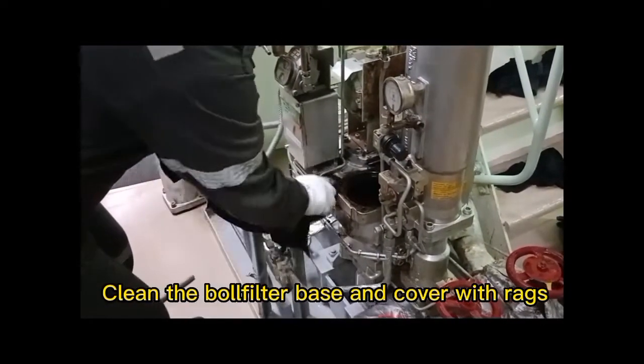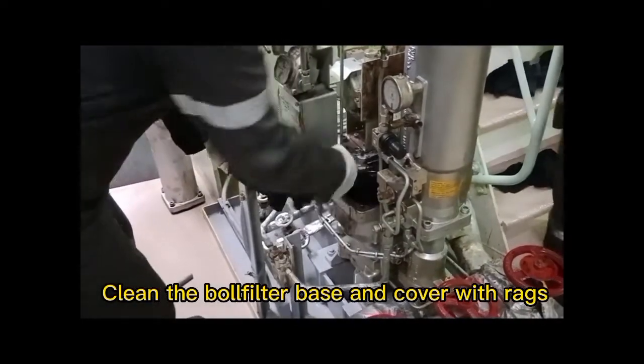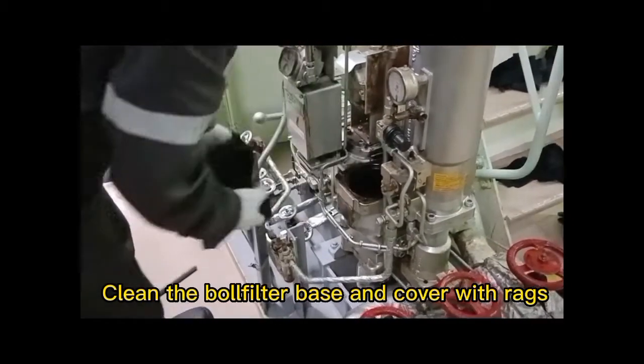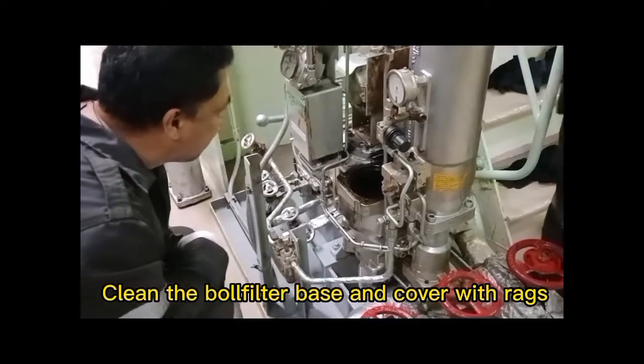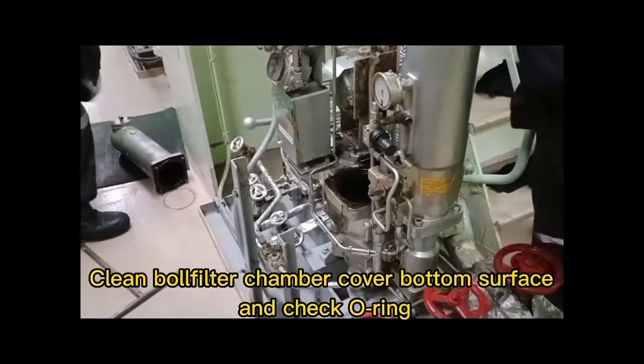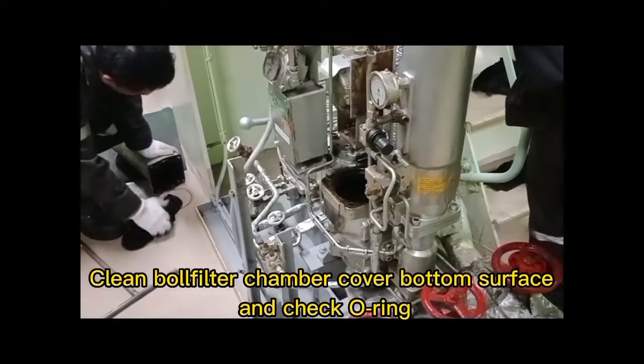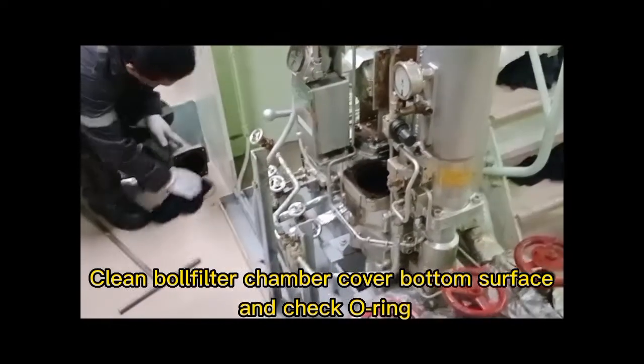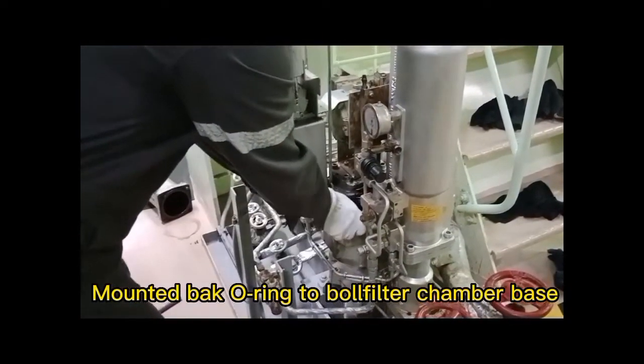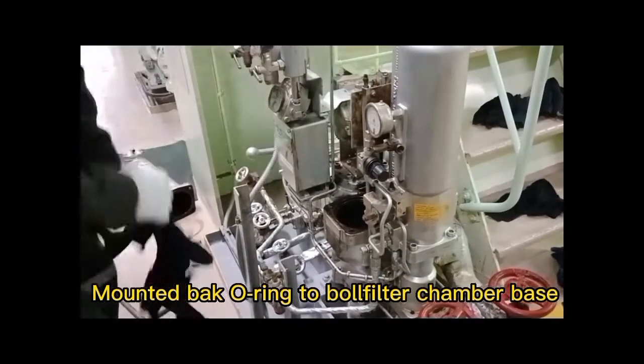Clean the Boll filter base and cover with rags. Clean the Boll filter chamber cover bottom surface and check the O-ring condition. Then mount back the O-ring to the Boll filter chamber base.